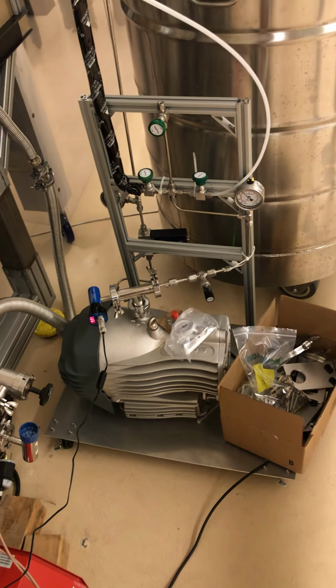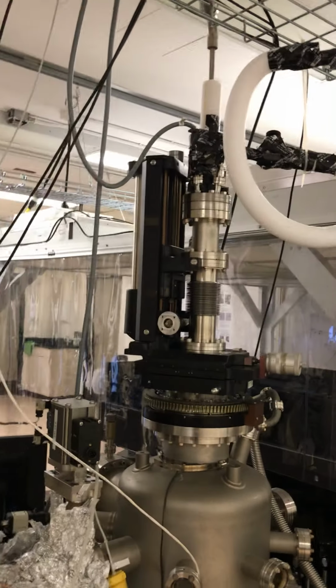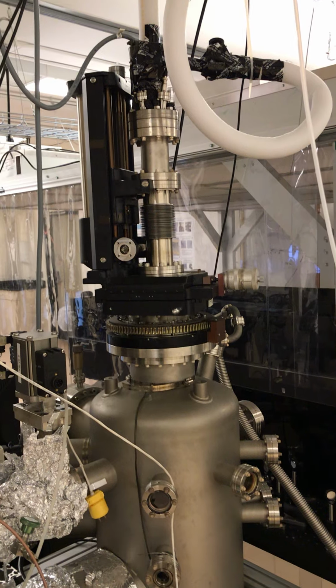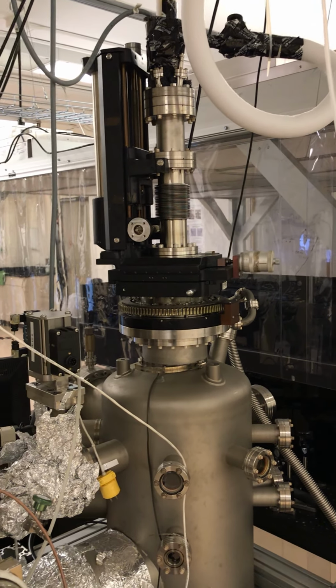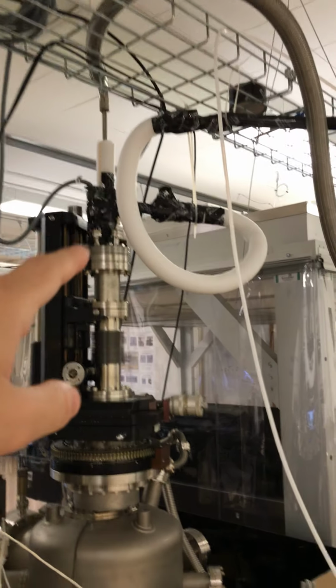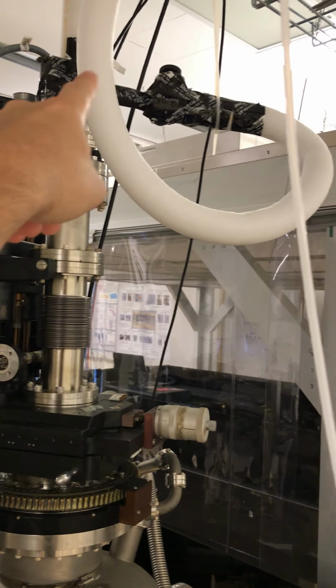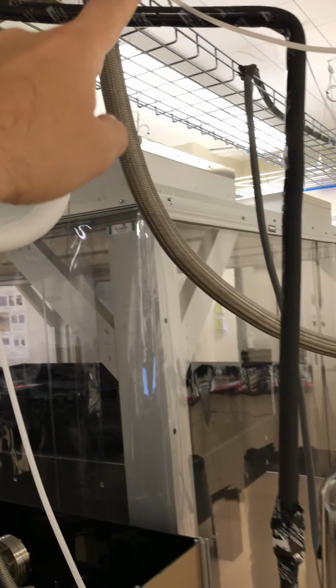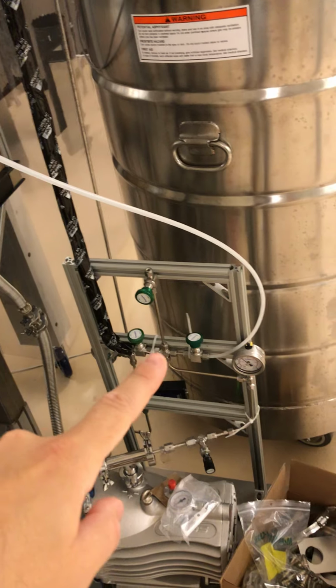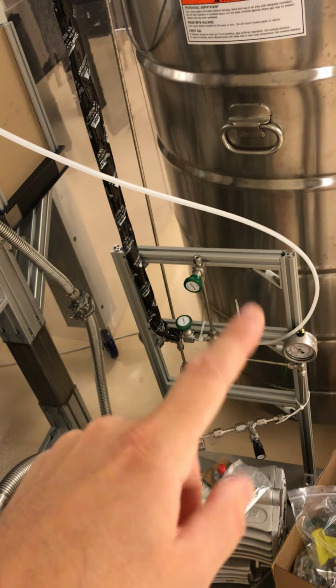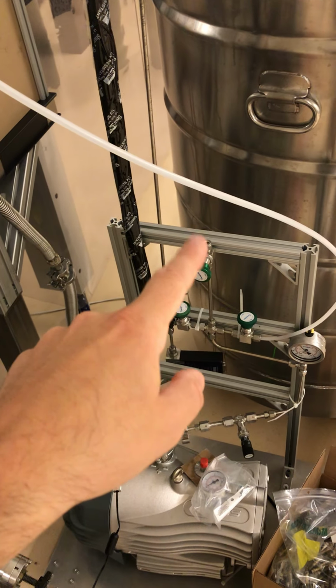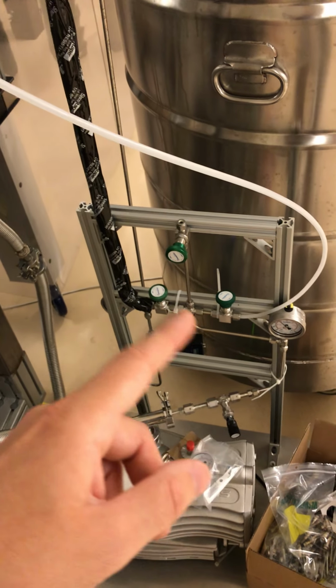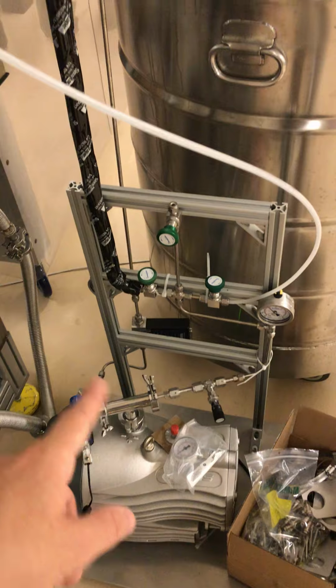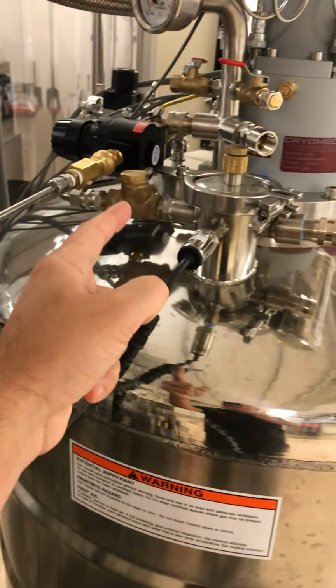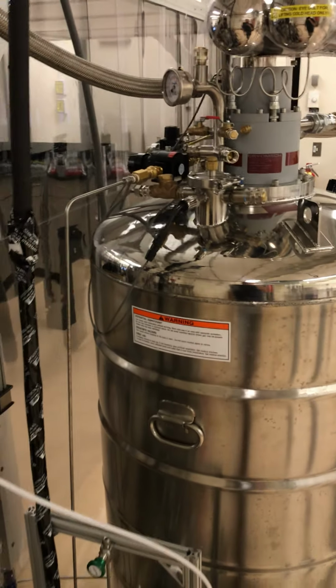This right here is a recirculation line that takes, once the liquid helium goes in there, cools the sample down to cryogenic temperatures. The liquid turns to gas. The gas gets collected through here, follows this, comes around like this, down through various valves. This plastic tube here is going to be a source of helium gas in case you want to put more liquid helium in here. This empty tube here is where we're going to connect the electron gun once it's built. Gas comes in through here, goes through this pump, comes back up this tube into the compressor to decompress back to its liquid helium state.